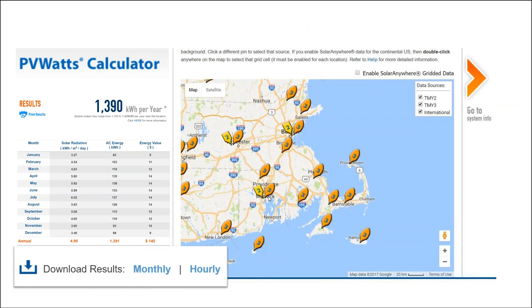Now, I think it's important to hammer home the fact that solar is done in hot environments, so that you don't go to a box store and buy off-the-shelf cable that doesn't have a high temperature rating because you're eager to run out and do your project. Have respect for buying cable that has more robust cable jackets than normal wiring, because solar is in a more extreme environment.